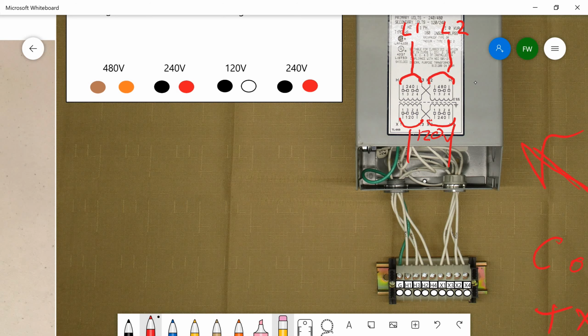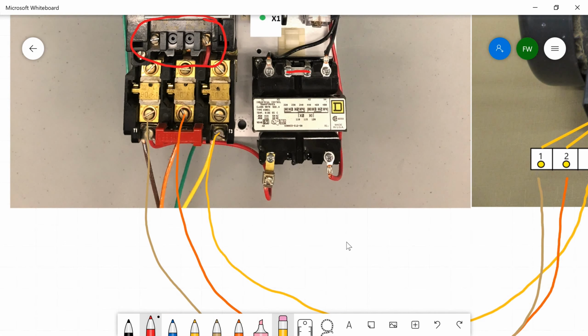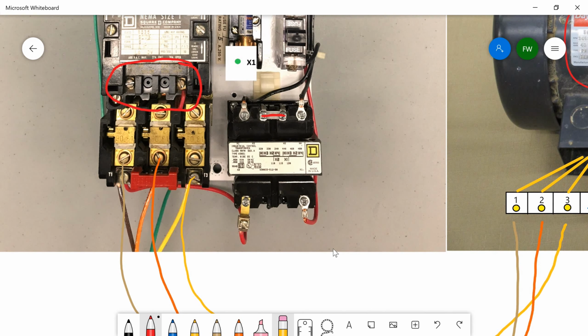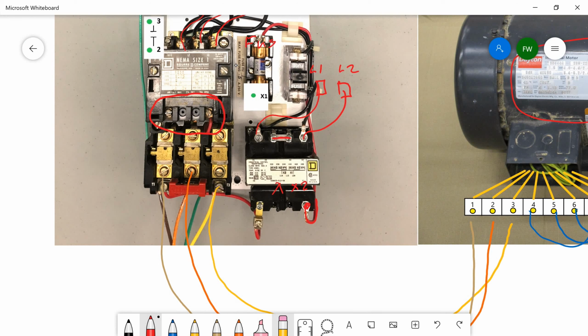Alright, so now let's take a look at this control transformer over here that's part of the combination motor starter. Okay, so one of the very first things that you notice is it's kind of hard to see, but on the input side of this combination motor starter, we're going to have two lines coming in. That'll be coming from our L1 and our L2 on the three-phase, three-wire system, and we're going to have two fuses. That's protecting the primary side of our control transformer. Now on the output side, if you look at this guy here, there's an X1 and X2 coming out. So here we have our hot coming out and going over to the fuse. This fuse here, you can see how the control transformer feeds into that fuse, and then we have a terminal on the secondary side there labeled X1.